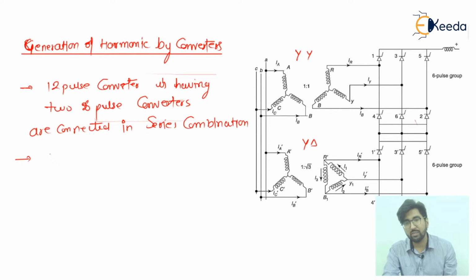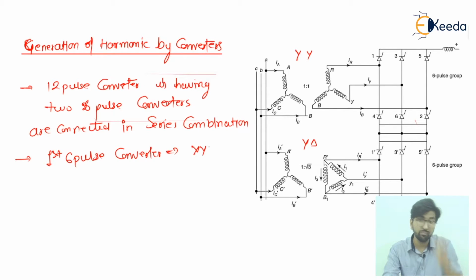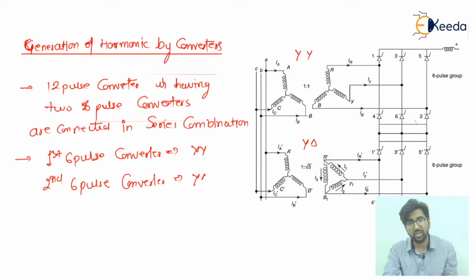The first 6 pulse converter is actually connected into a star and star combination. And if I talk about the second 6 pulse converter, it is actually connected in star and delta. These are connected in such a way to give a phase difference of 30 degrees.